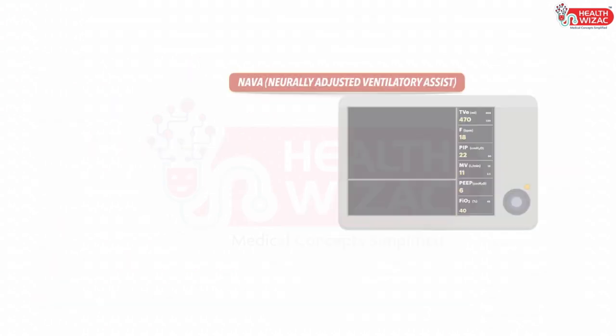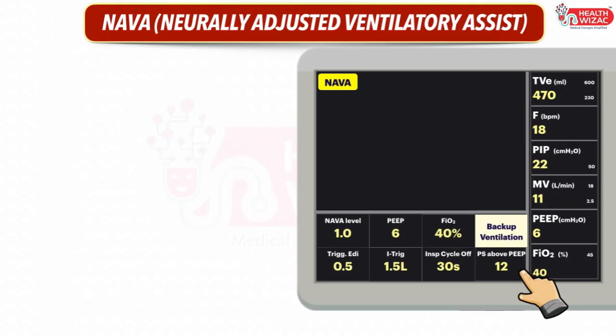In NAVA mode, we have to set NAVA level, PEEP, FiO2, Edi trigger, inspiratory trigger, inspiratory cycle off time, PS above PEEP, and backup ventilation settings.